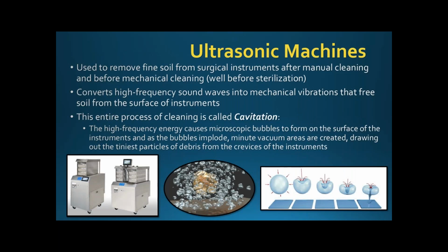A lot of instruments anymore, especially some with fine grooves, have in their IFU that they need to be placed into an ultrasonic. The ultrasonic is going to help remove all that fine soil and debris that's in your instrumentation. So if you do not have an ultrasonic in your facility, you should probably find out if any of the instruments you are using require it in their instructions for use. You want to make sure you are using the ultrasonic as intended. It's really just to help you get all that fine stuff out.